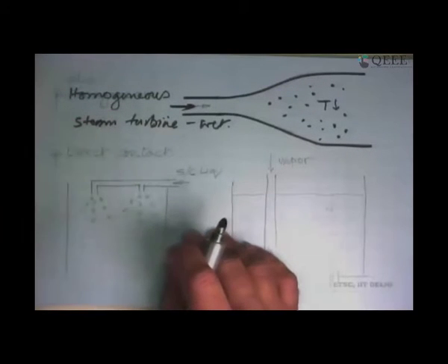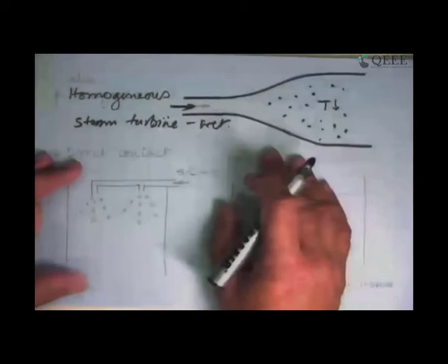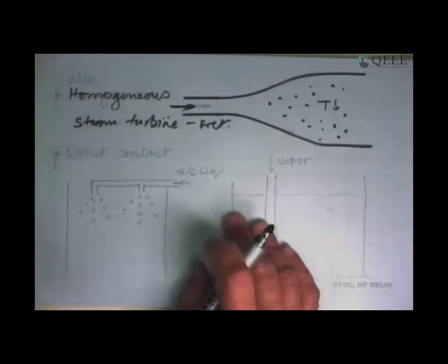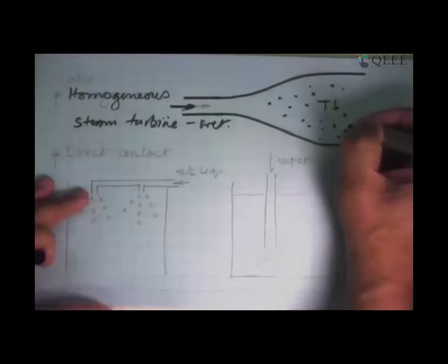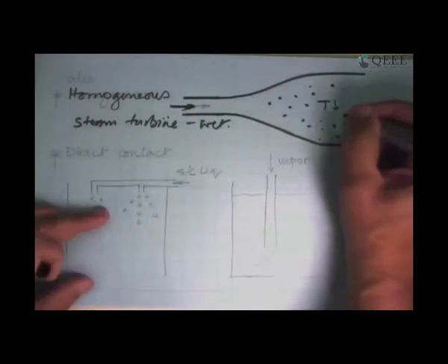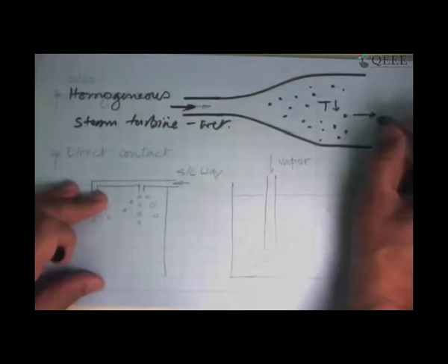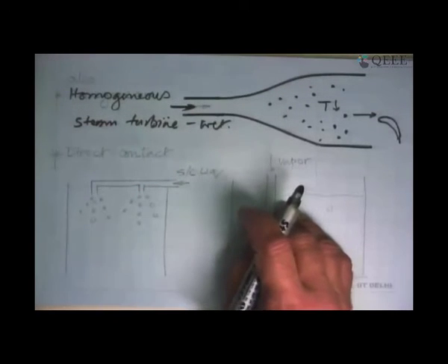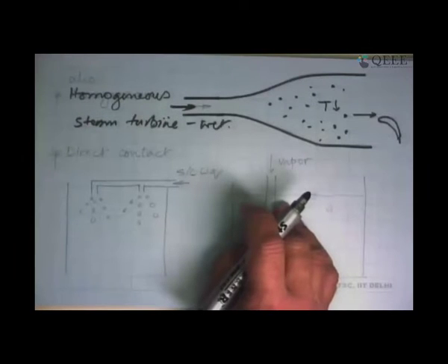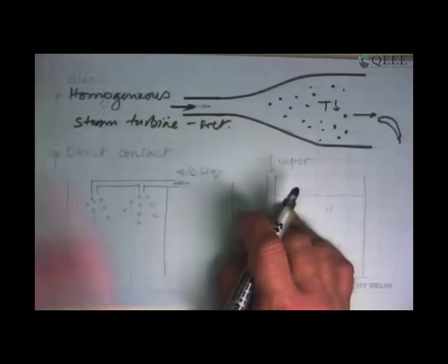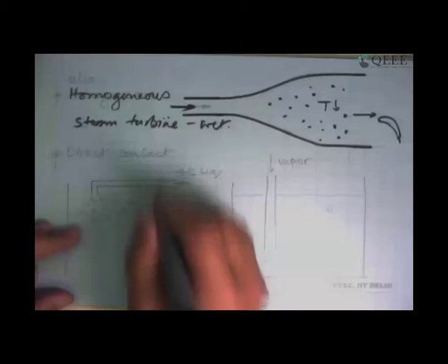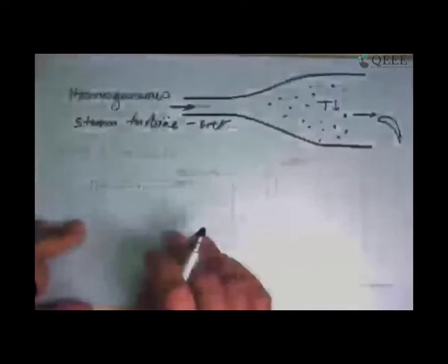In most nuclear turbines, you have almost the whole turbine operating with wet steam. So you are always going to have a lot of droplets moving through the steam in the blade passages. For a machine like that, which is rotating, these are small droplets, maybe 100 micrometers, 200 micrometers, but they have a finite mass and a very high velocity, and if they hit the blade of a turbine, that could cause erosion. That is something engineers have to worry a lot about, and they do all sorts of things to prevent erosion, and you have to replace blades if they get broken or cracked. So that is another application where this type of condensation takes place.